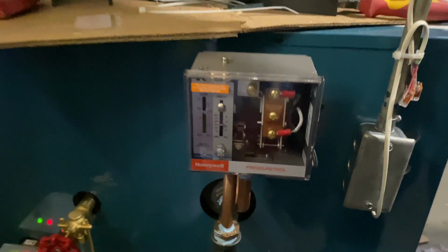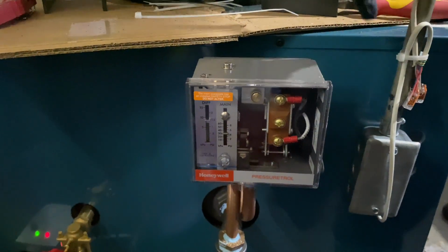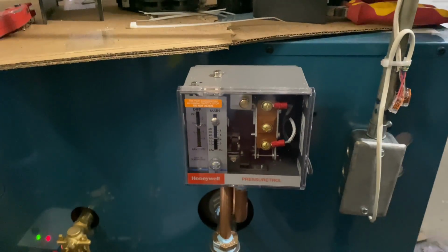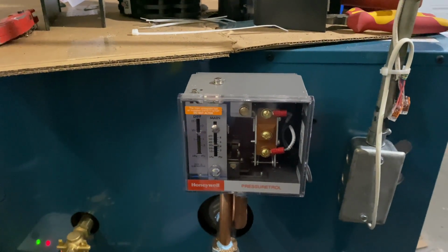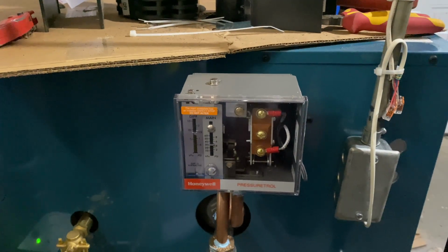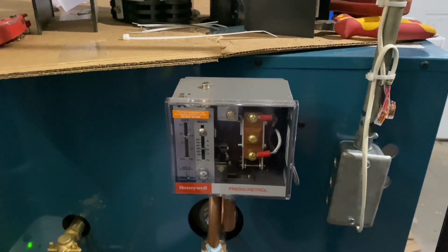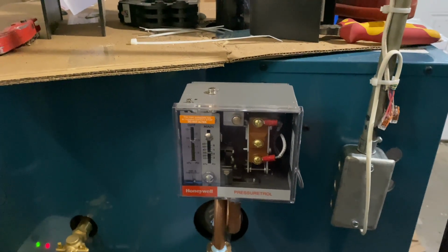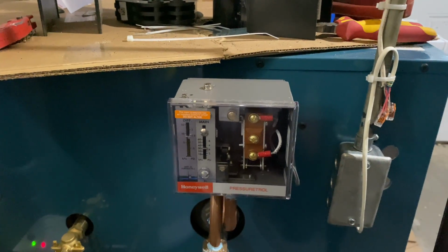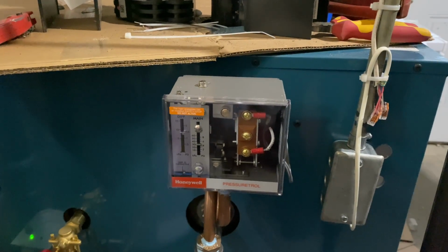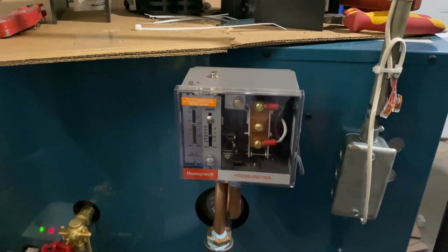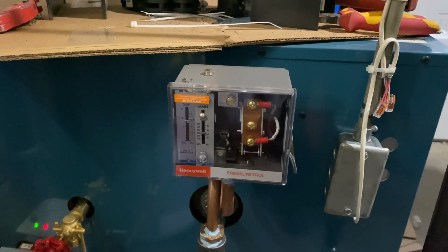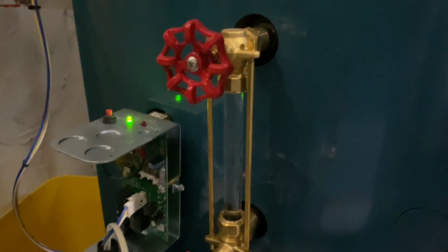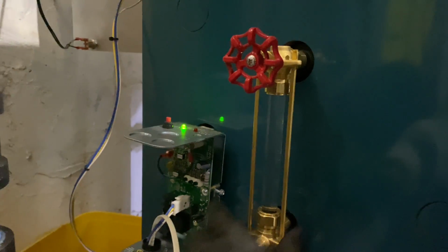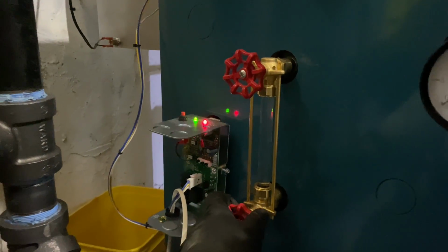Now, on a side note, I'm a big fan of Dan Holohan and the lost art of steam heating, and his other books called We've Got Steam Heat. And one of the things that Dan Holohan and other dead men of steam talk about is having a Pressuretrol set at 0.5 pound to 1 psi of pressure. Jacking up the pressure. Did I overfill the boiler? Yes, I did. We need to drain some water in the boiler. There's a bucket over there.